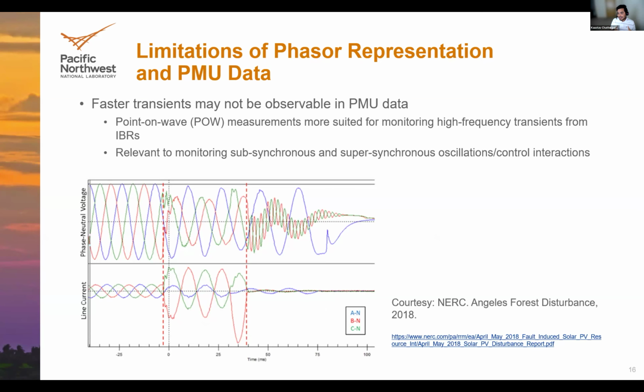Also, these devices have filters that cut off frequencies above a certain range, so you're limited to monitoring somewhere around 5 Hz or below. Anything with higher frequency in its waveform won't be reproduced, and this becomes important as we keep introducing IBRs, which bring subsynchronous and supersynchronous oscillations into the system.